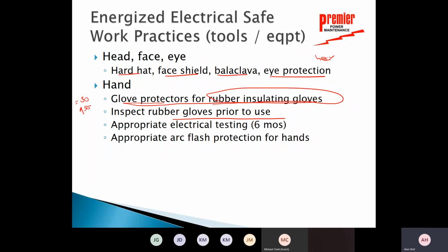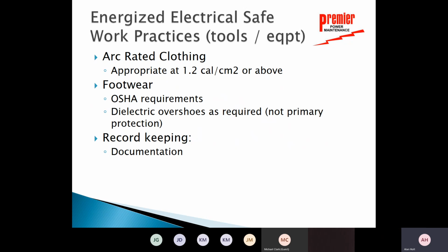We have to inspect those before we use them. We need to make sure that the date stamp on those is less than 6 months. And we make sure that we've got appropriate arc flash protection of our hands. If we are in a situation where we're not using gloves, we're not testing, but we are inside that arc flash boundary, we can't be there barehanded. Even if you're a spotter, somebody assisting, if somebody's actually working in that area or doing an activity that could create an arc flash, we have to have protection for our hands. We can use the arc flash resistant gloves, but certainly our rubber gloves with our leather outers will suffice for that. Arc flash rated clothing, 1.2 calories per square centimeter and above.